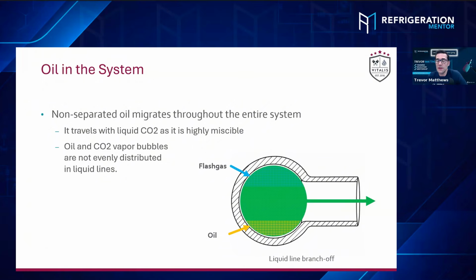Yeah, totally agree. Got a great question here because at the beginning we talked about PAG 68 and POE 85. Does that make a difference in this? I would assume you're still going, it doesn't matter the oil, the way you're going to pipe it. You're going to want it off the side. It doesn't make a big difference in the vapor lines, but it makes a big difference in the liquid lines because it's totally separating the PAG oil versus the POE oil. So way more important to not build little oil traps inside the liquid line.